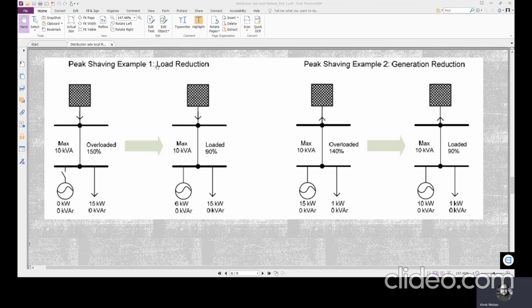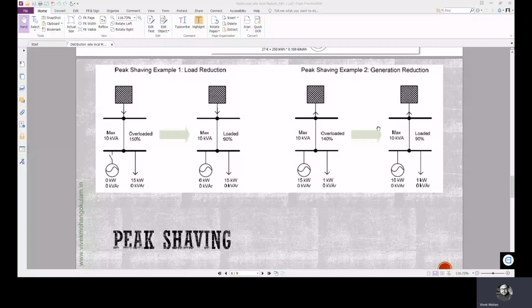That is what is written here, load reduction. So by means of load reduction, we are trying to shave the peak. Now, in the second example, we have 15 kilowatts local generation and 1 kilowatt is the local load. So 14 kilowatts active power is in excess and 14 kilowatts is pumped to the upstream grid. So that's why this is 140% overloaded now.